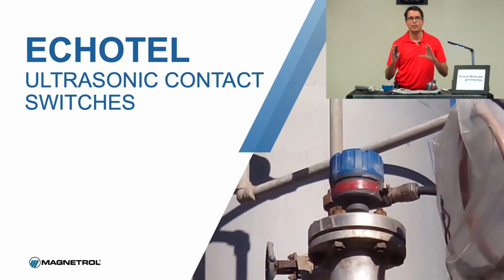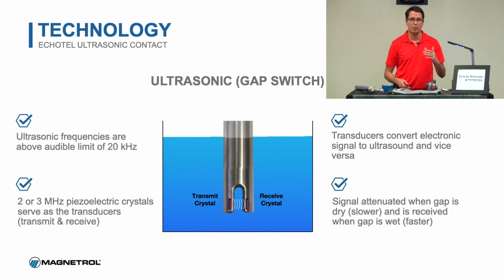So I think Bill alluded to it at the beginning. We've had a couple different transmitters. This is a point level device, but you can actually do some controls with this device. High level, low level, combination of control, pump on and off. It's actually a very common device to control levels. I've seen it in all kinds of applications, sumps, underground tanks, seal pots, just a variety of different applications that you can target with this device.